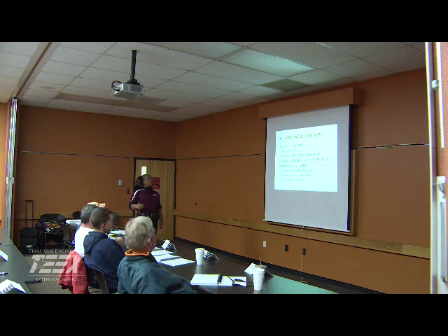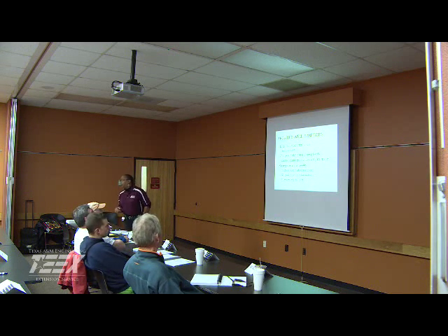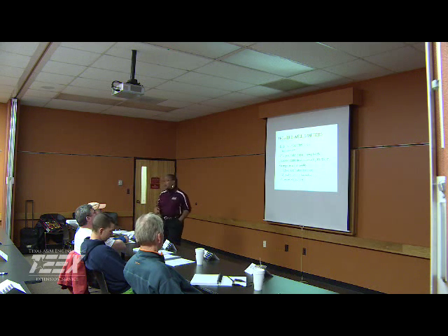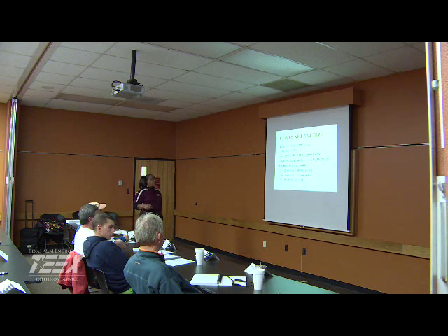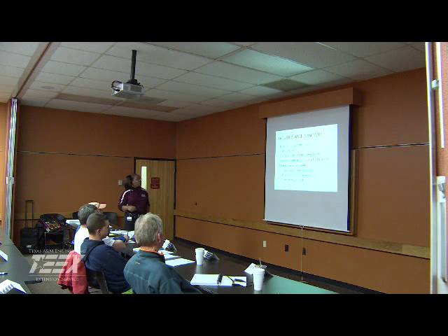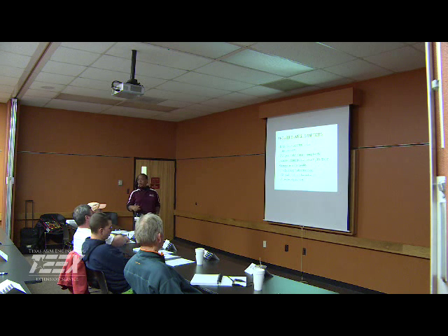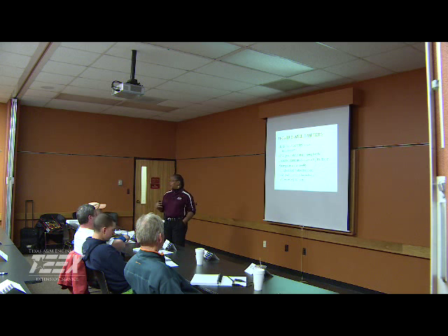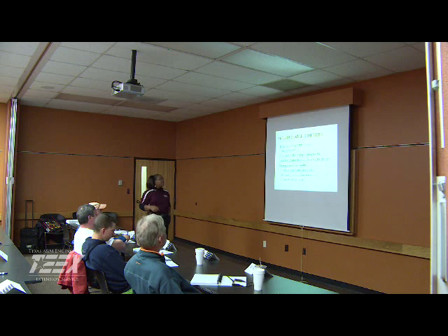All right, so trouble symptoms, things that you should be concerned about when you start seeing this. If there is a drop in pump performance, again, that is indicated by a reduction in the gallons per minute. A warning sign. Changes in your static and pumping levels. Something is going on, you need to do additional investigation. Or if you have increased sand production or water turbidity, because we've already said ground water should be fairly clear because of, again, the percolation process through various layers.